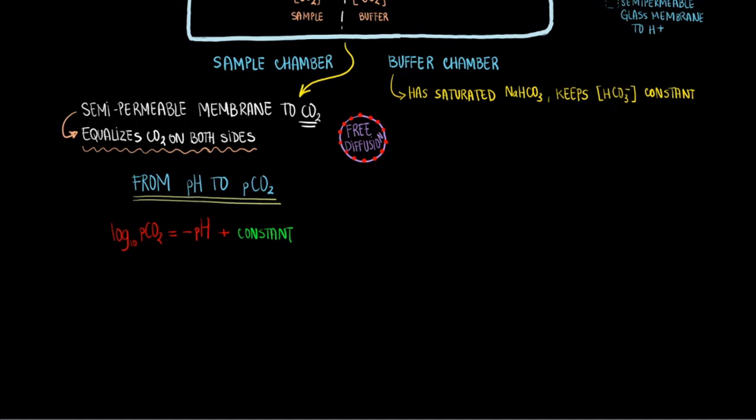The constant in the equation is dependent on the concentrations of hydrogen ion, bicarbonate ion, and CO2. But this is not actually something you need to worry about, which is why I simply labeled it as constant. You will actually measure this constant when you calibrate the Severinghaus electrode using a sample with a known value of partial pressure of CO2.